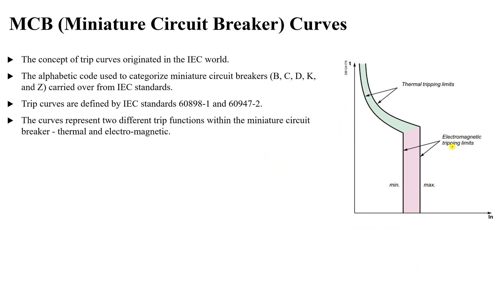There is also the electromagnetic part of the curve, where the tripping time is very, very small — almost instantaneous. This occurs between 3 to 5 times the rated current. For example, if the circuit current reaches 3, 4, or 5 times the rated current, the miniature circuit breaker will instantaneously trip the circuit.